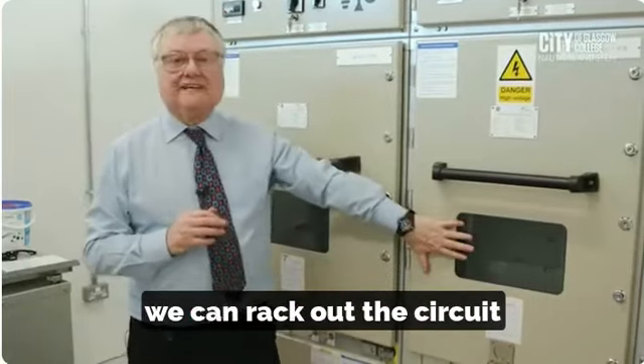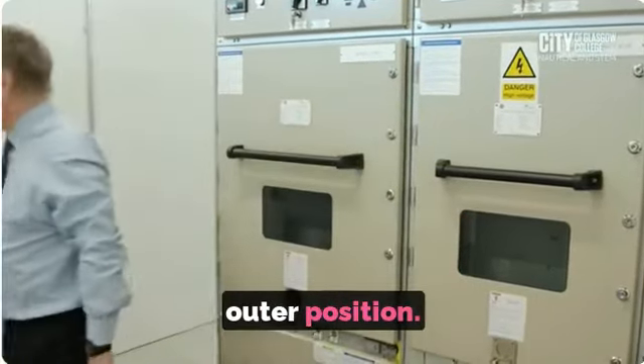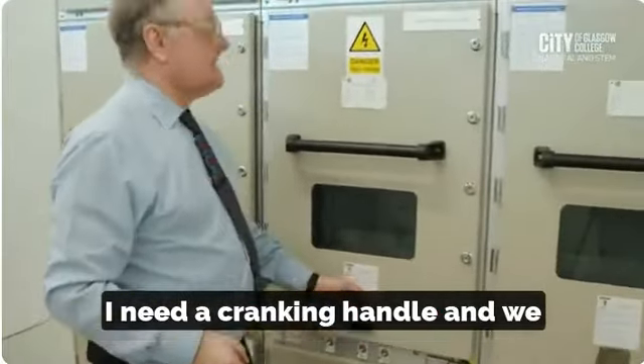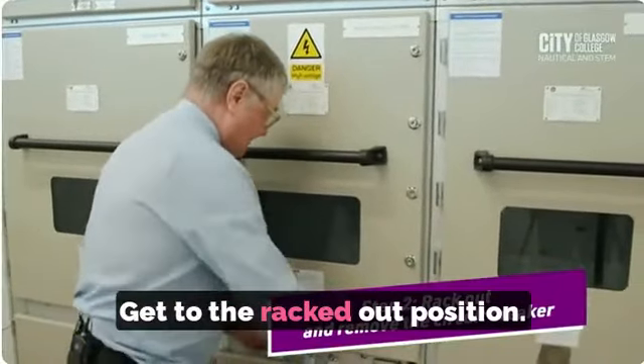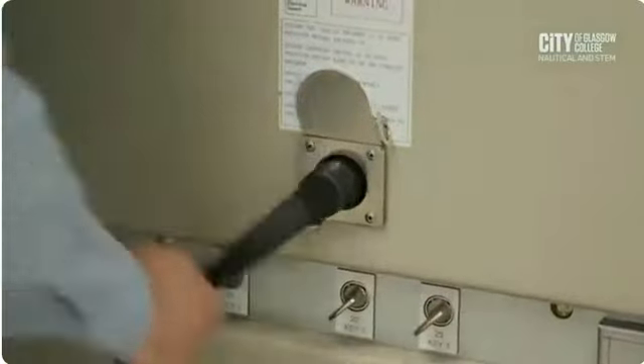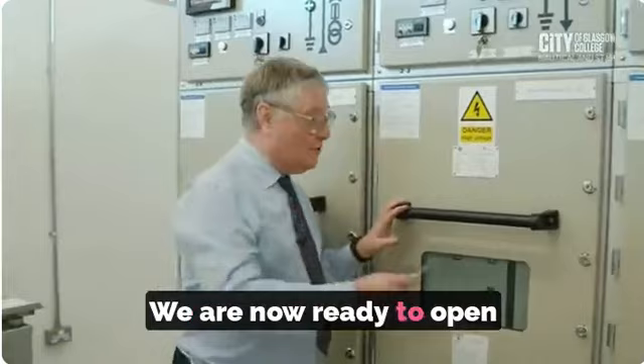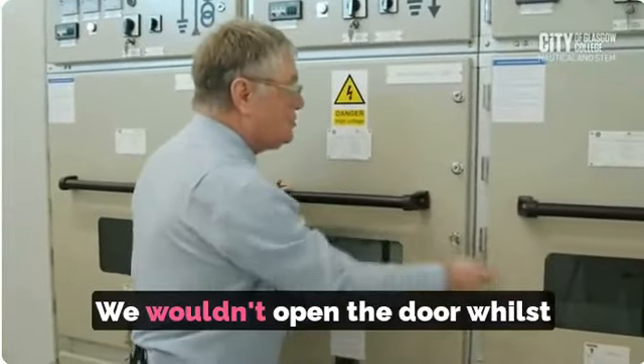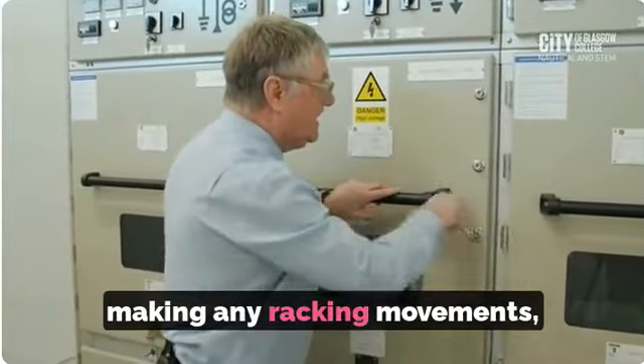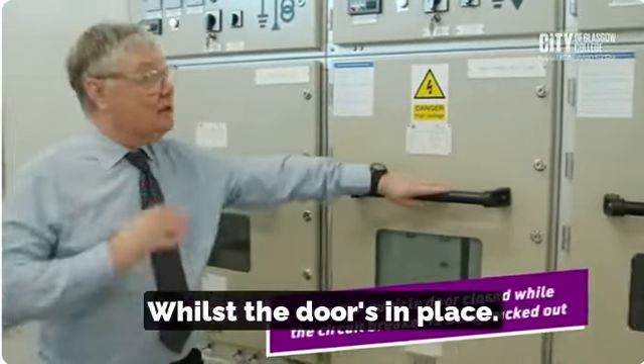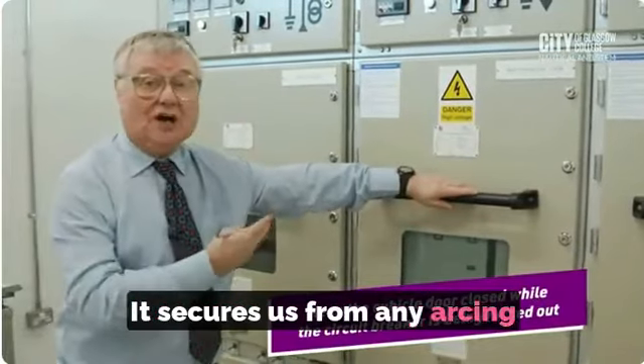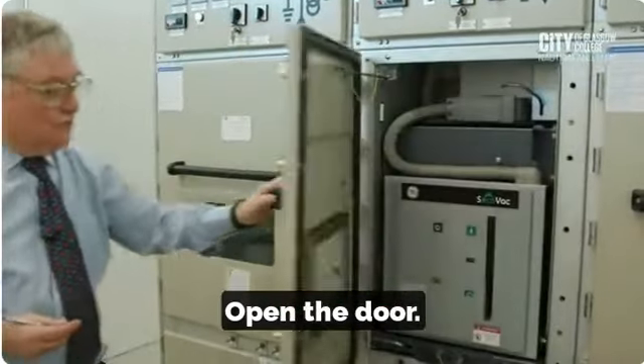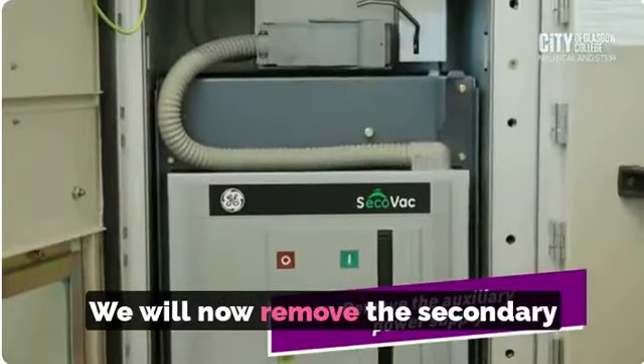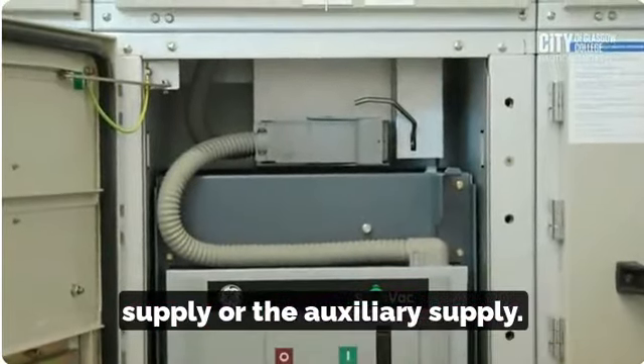We're now in the position where we can rack out the circuit breaker to the racked out position. For this, I need a cranking handle, and we will rack out the circuit breaker to the racked out position. We are now ready to open the actual door. We wouldn't open the door whilst making any racking movements, either in or out. Whilst the door's in place, it secures us from any arcing incidents that could happen. Then open the door.